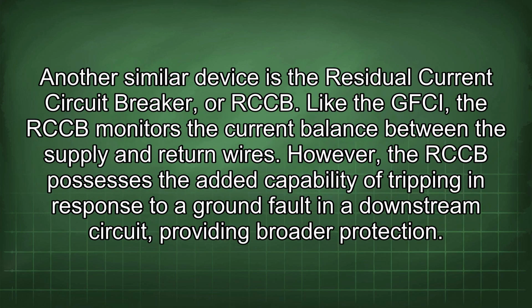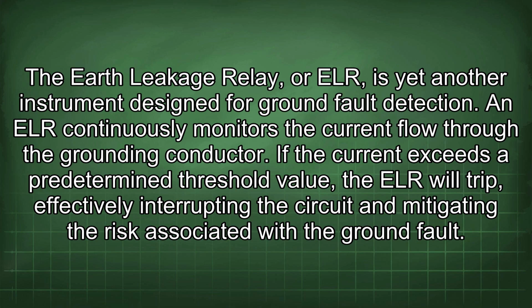Another similar device is the residual current circuit breaker, or RCCB. Like the GFCI, the RCCB monitors the current balance between the supply and return wires. However, the RCCB possesses the added capability of tripping in response to a ground fault in a downstream circuit, providing broader protection. The earth leakage relay, or ELR, is yet another instrument designed for ground fault detection. An ELR continuously monitors the current flow through the grounding conductor. If the current exceeds a predetermined threshold value, the ELR will trip, effectively interrupting the circuit and mitigating the risk associated with the ground fault.